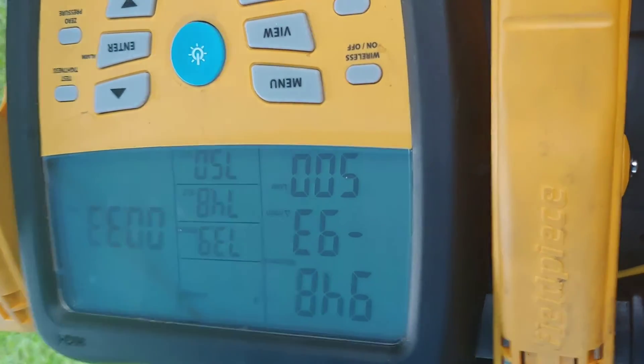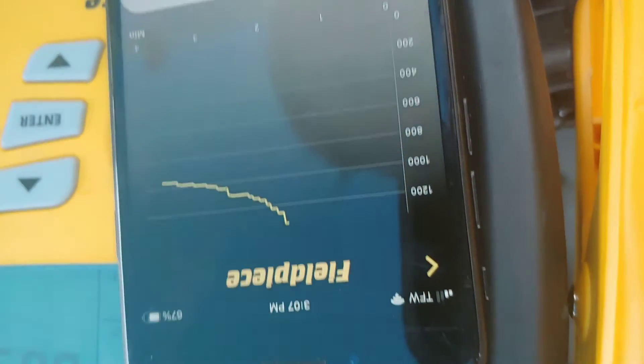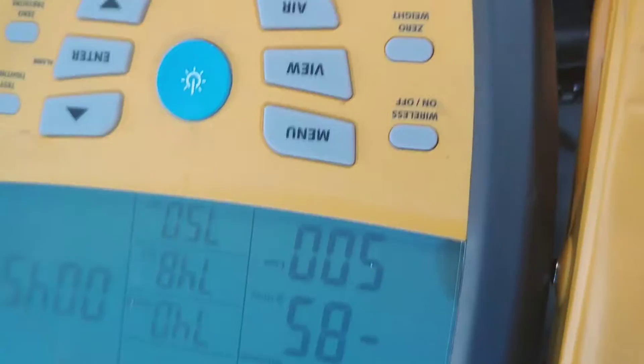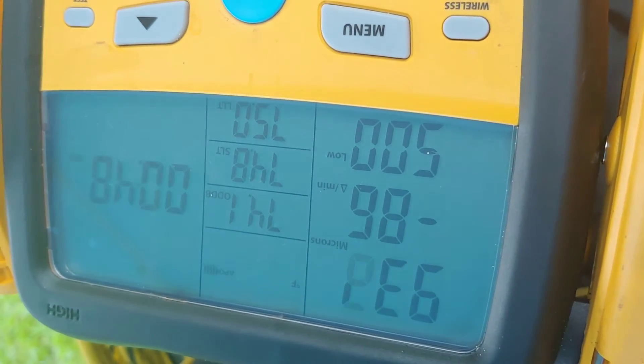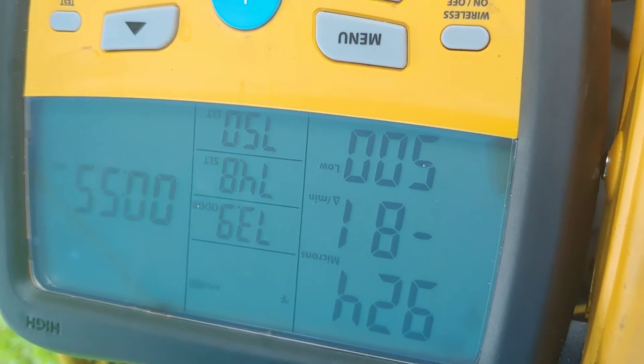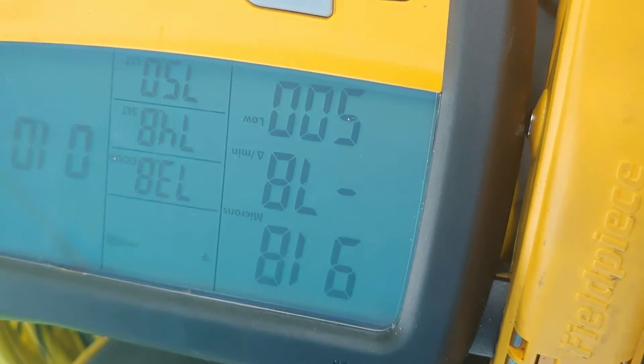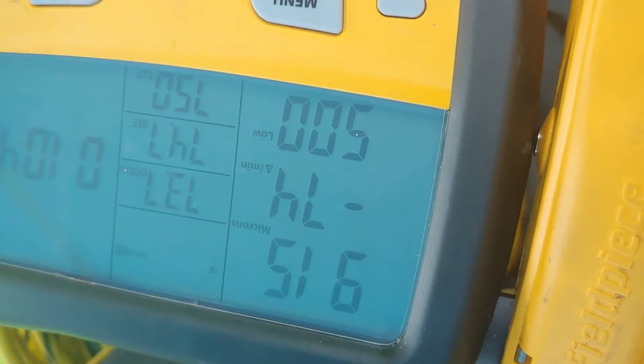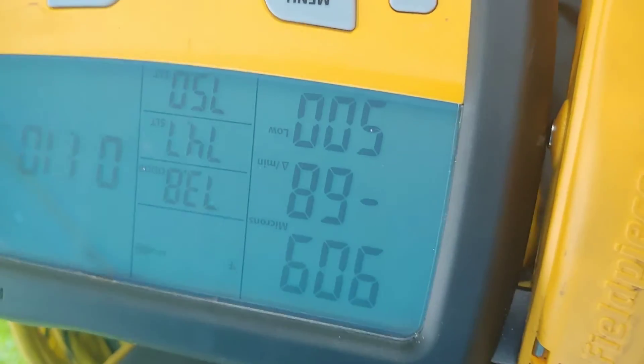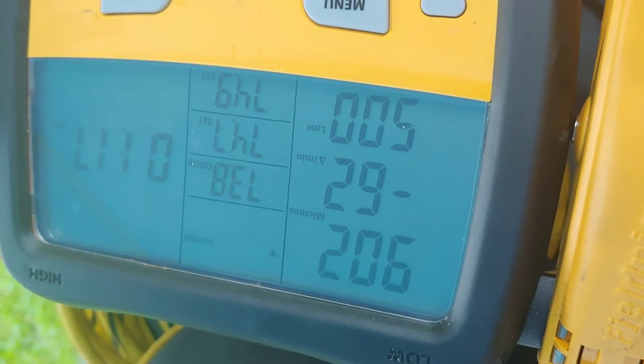That curve's kind of leveling out a little bit. It's wet today, 100% humidity out here — not an ideal day to pull a vacuum. But sometimes we don't get ideal days. Yesterday, when you went to go do that blower, we had to go do a condensate pump and it was raining. The water was going right underneath the house, all muddy under there — it was like crawling on a waterbed.